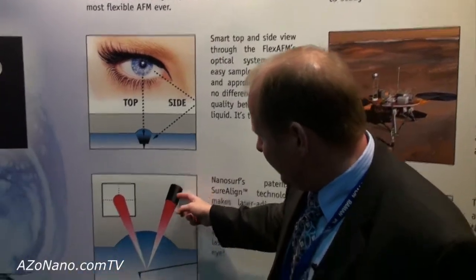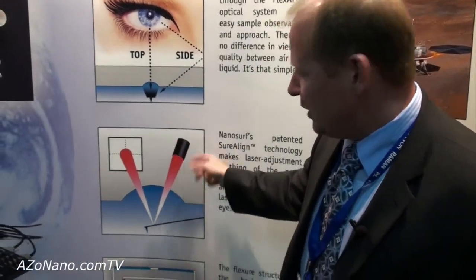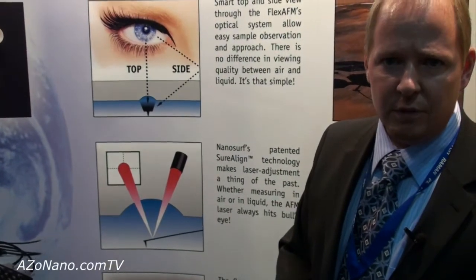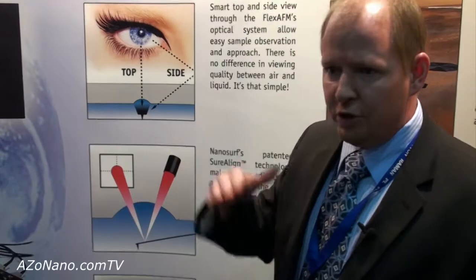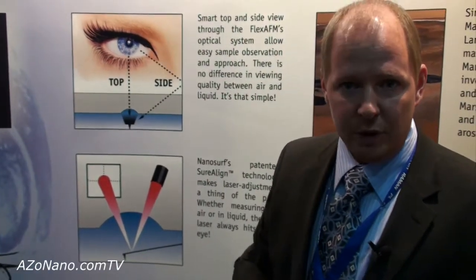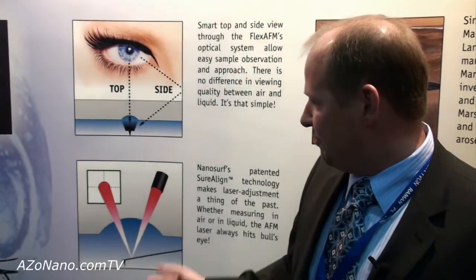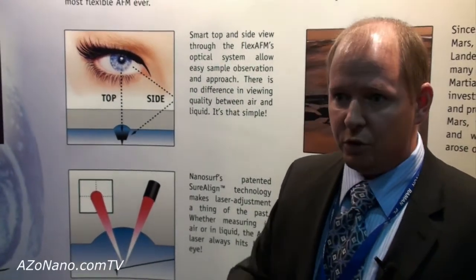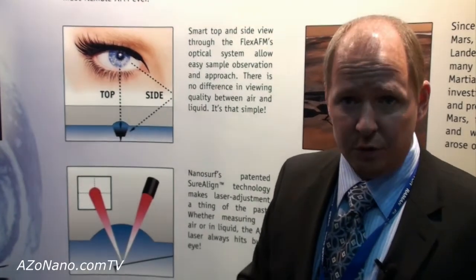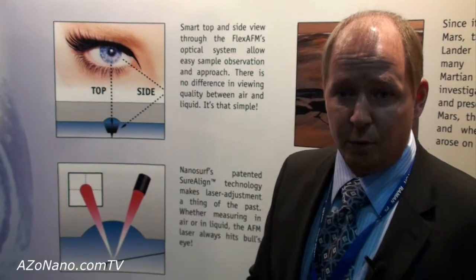We also have our patented SureAlign technology where the laser that attaches to the cantilever also descends into the liquid and doesn't have to be realigned. This is the only AFM which can descend into liquid without adjusting the laser afterwards, which saves user time and eliminates that cumbersome operation.